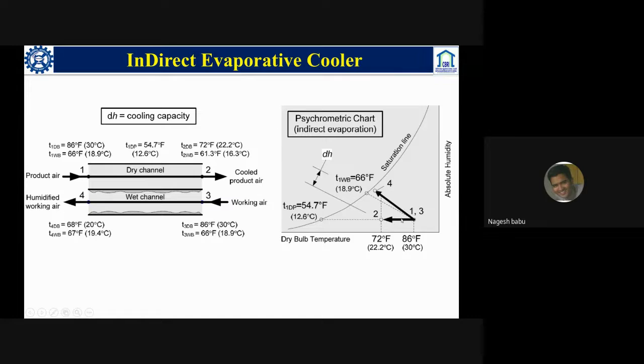If we look at an indirect evaporative cooler, though its temperature is reducing, its humidity is not increasing. So it is a type of cooler for when we don't want an increase in humidity, but only a reduction in temperature. Then we can go for a typical indirect evaporative cooler. This is also applicable for warm and humid conditions where there is a lot of humidity.